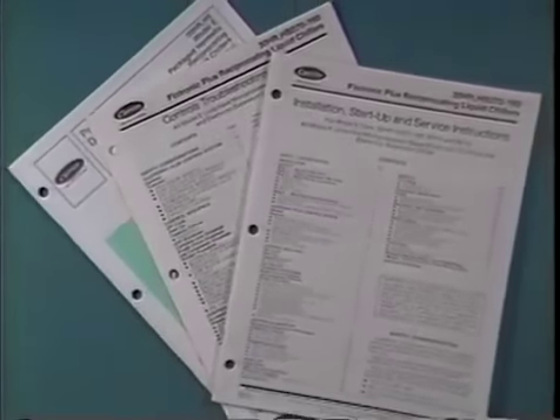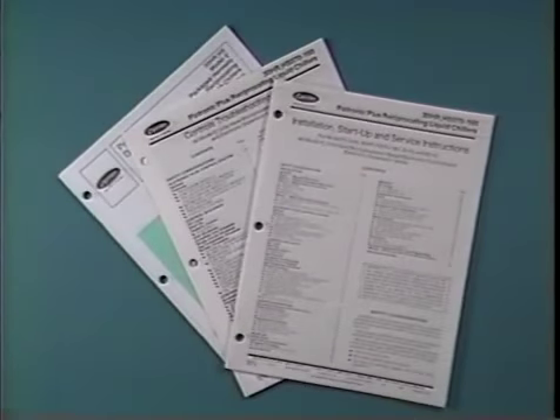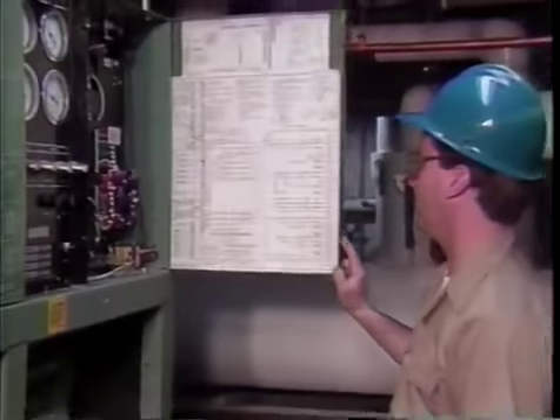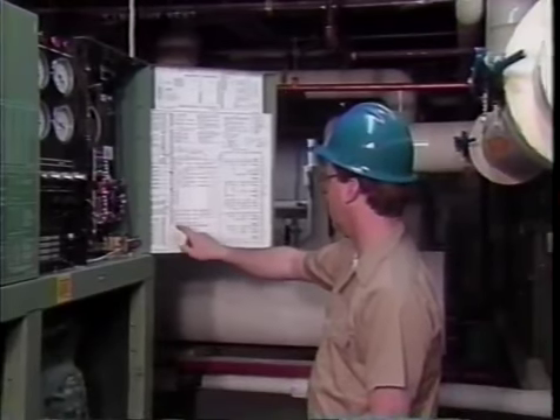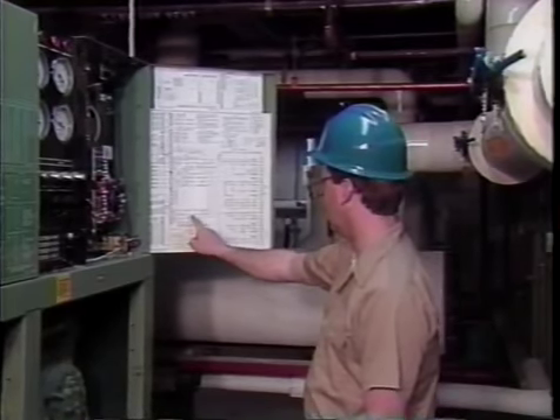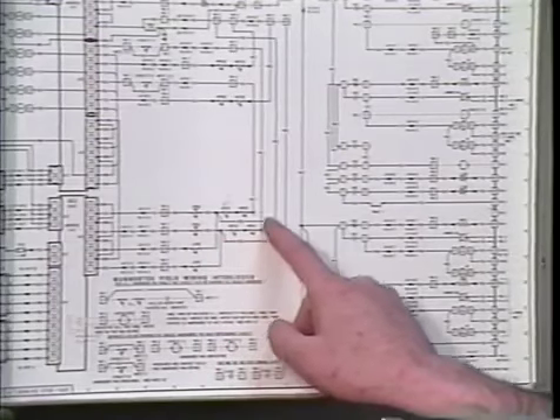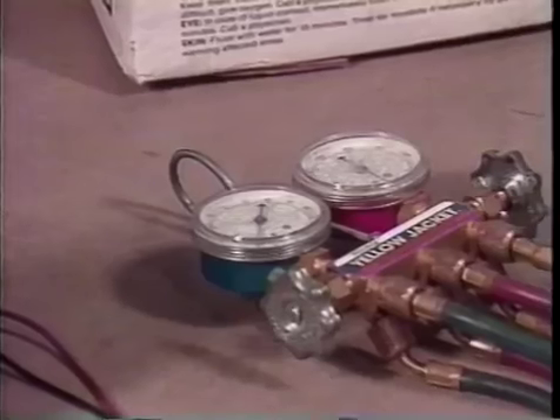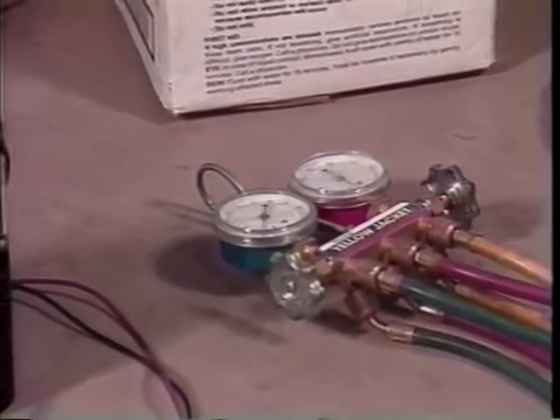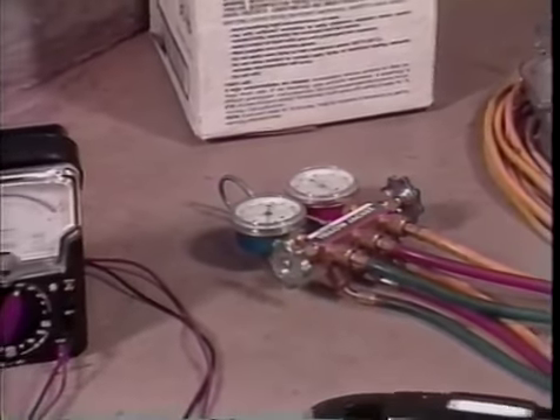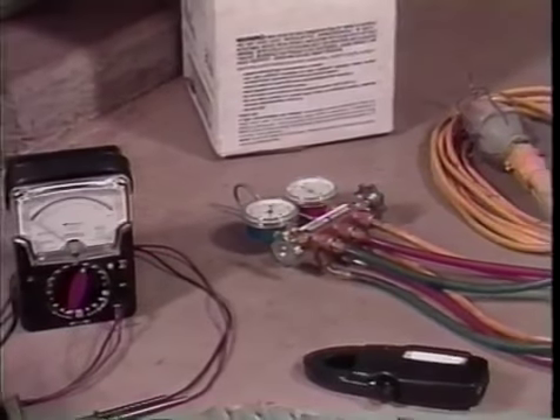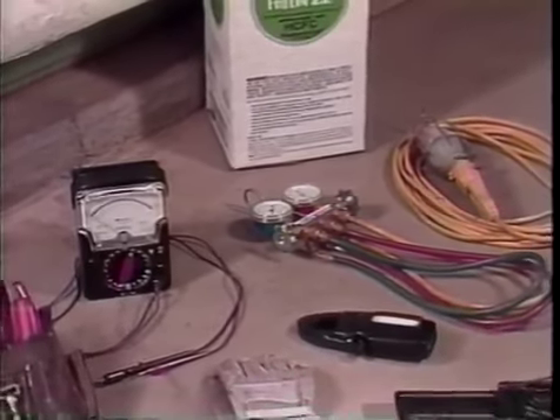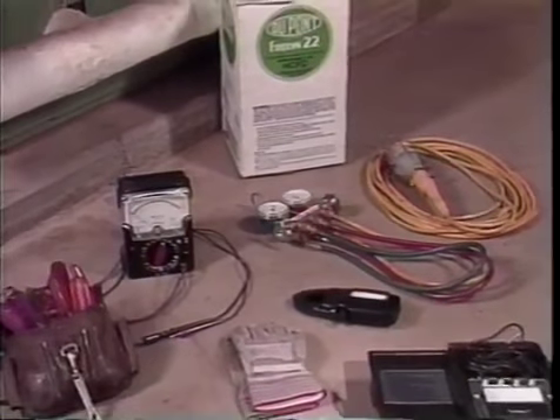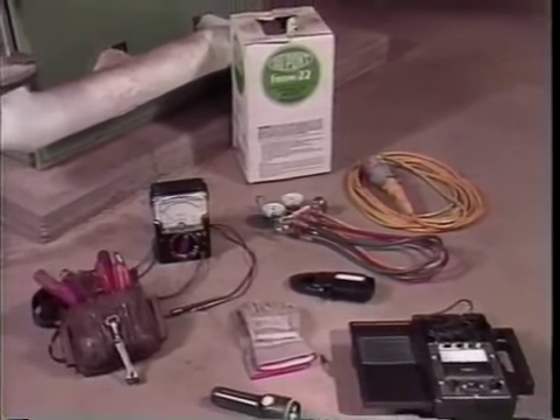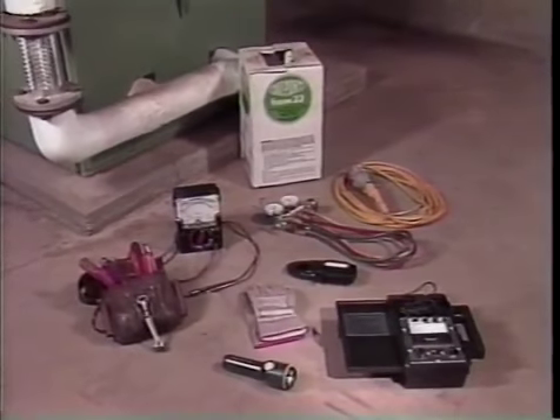Before the visit, you should obtain the necessary service and maintenance literature for the unit. Wiring diagrams are essential and will normally be found on the inside of the control panel door. Contact your distributor for any necessary literature and talk to your distributor service manager if you have any questions regarding the operational check. Have the following tools available at the time of the visit: an accurate gauge manifold set, volt-ohm meter, clamp-on ammeter, digital temperature probe, the correct refrigerant for the unit, normal hand tools, flashlight, trouble light.